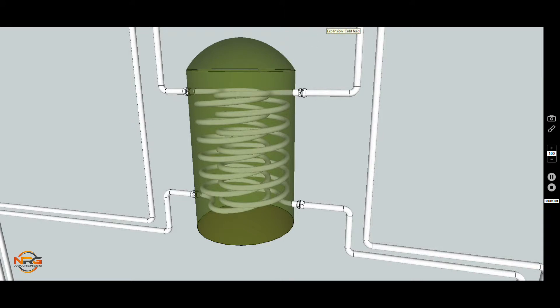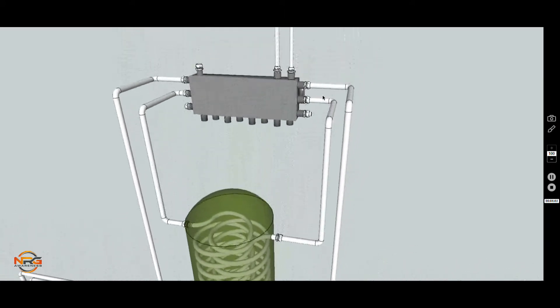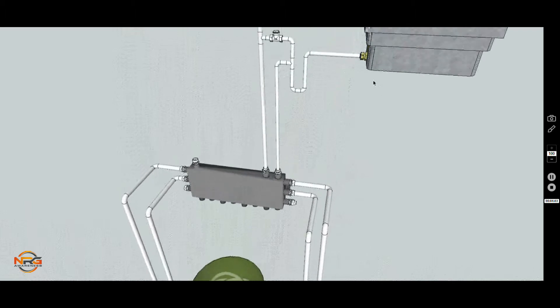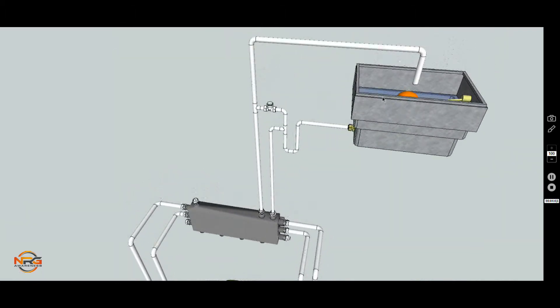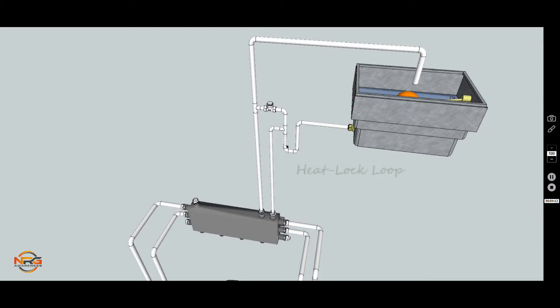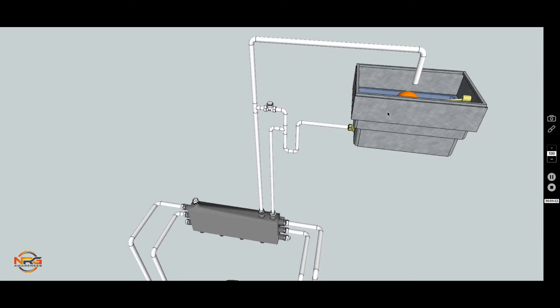If you have an open system, you obviously will have to have an open storage tank in the attic, which will contain the stored water, a mains feed-in to top up that water, a cold feed out into the system which would go through a heat lock loop to make sure no hot water will inadvertently rise into the tank and heat the contents of the tank, which would cause evaporation and therefore cause more fresh water to be introduced. Fresh water into an open system is always a problem because it will bring oxygen in with the water, and that oxygen will detrimentally affect the iron parts, the ferrous parts, such as radiators, manifolds, oil boilers, or whatever are made of iron parts in the system like pumps.